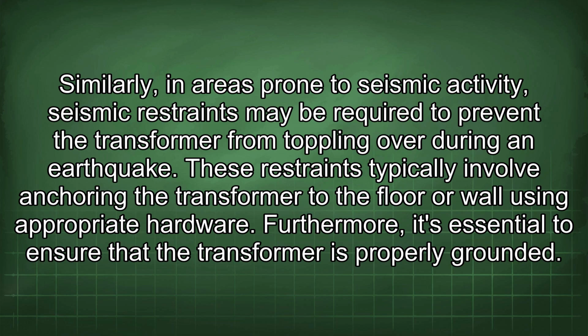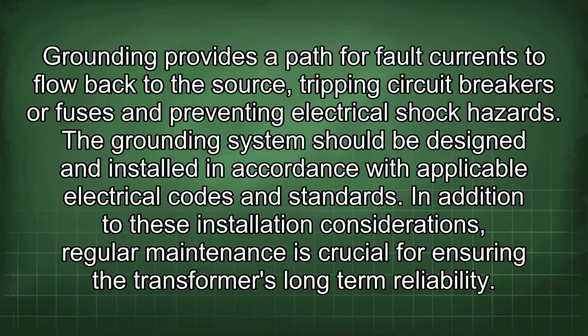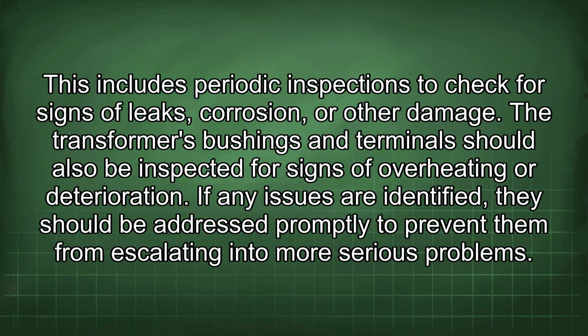Furthermore, it's essential to ensure that the transformer is properly grounded. Grounding provides a path for fault currents to flow back to the source, tripping circuit breakers or fuses and preventing electrical shock hazards. The grounding system should be designed and installed in accordance with applicable electrical codes and standards. In addition to these installation considerations, regular maintenance is crucial for ensuring the transformer's long-term reliability. This includes periodic inspections to check for signs of leaks, corrosion, or other damage. The transformer's bushings and terminals should also be inspected for signs of overheating or deterioration. If any issues are identified, they should be addressed promptly to prevent them from escalating into more serious problems.